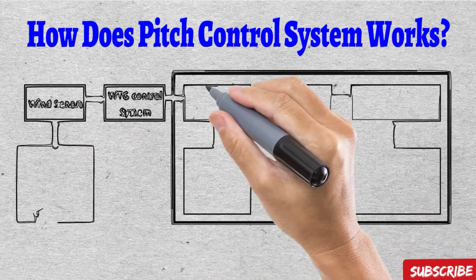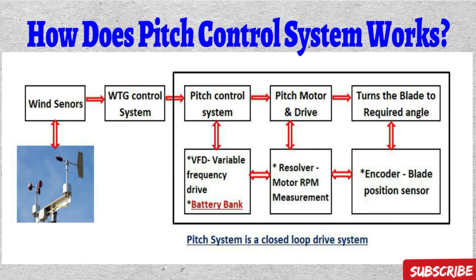The pitch system is a closed-loop drive system and mainly depends on wind sensors — anemometers and wind vanes. The wind sensor gives actual values to the WTG main control system. The main controller calculates the actual blade angle and sends angle commands to the pitch controller. The pitch controller has a VFD (variable frequency drive) and a battery bank, which plays an important role. The pitch controller gives supply to the pitch motor to set the required blade angle. The pitch motor has a resolver to measure RPM, and an encoder in the hub unit measures blade angle position for each blade.